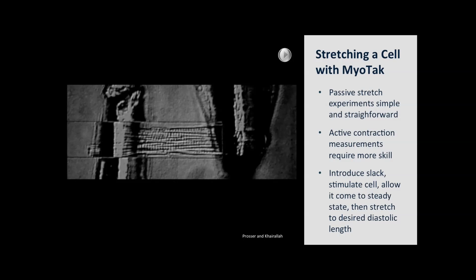And so for measurements of active contraction, before the first stimulated contraction, I recommend introducing some slack into the system. Move the rods closer together and remove any tension on the cell. And this is recommended particularly when working with rat and mouse cells, where the sarcoplasmic reticulum is overloaded with calcium in the quiescent cell. And there's a particularly large calcium release and contraction for the first few twitches before the cell reaches steady state. So by introducing slack in the system, you decrease the likelihood of the cell popping off the rod with that first massive contraction. You can then stretch the cell back to the desired sarcomere length upon reaching steady state and proceed with your experiment.